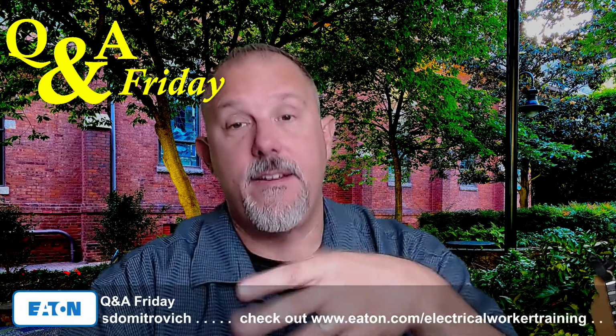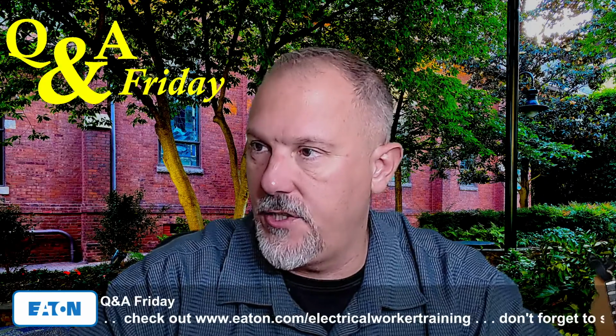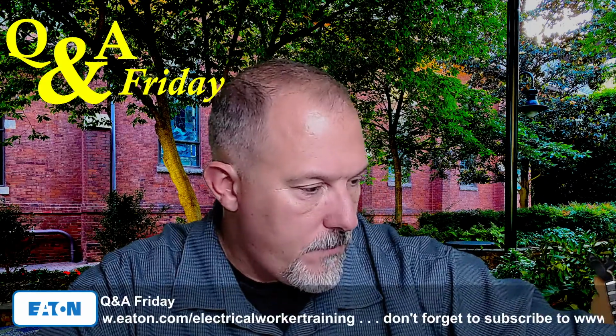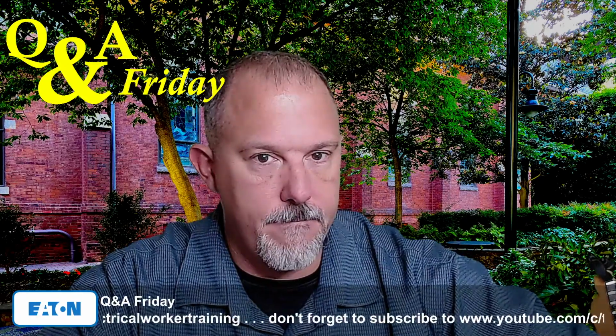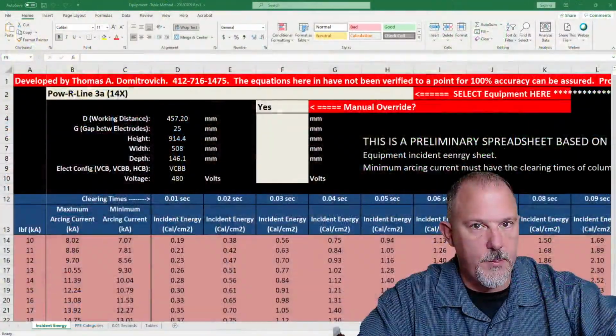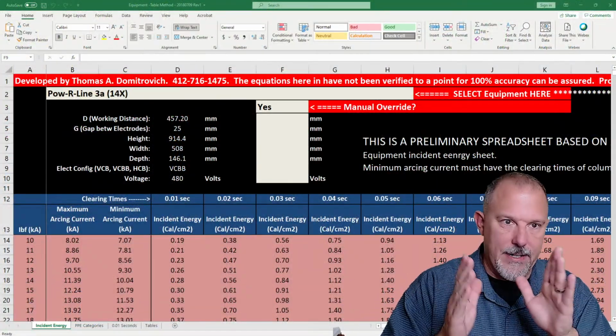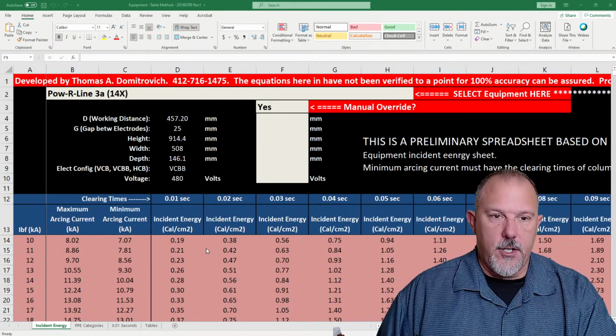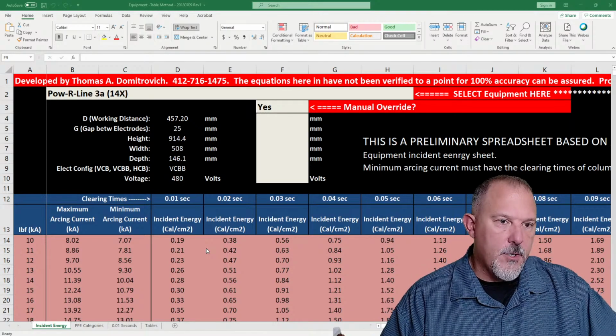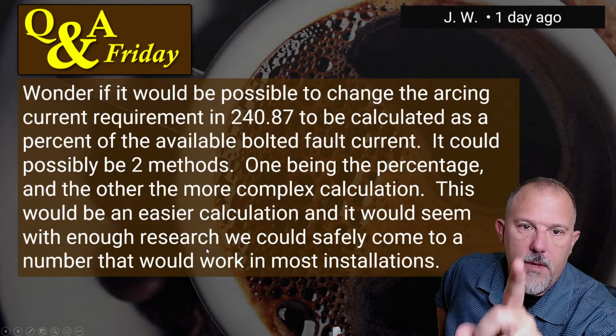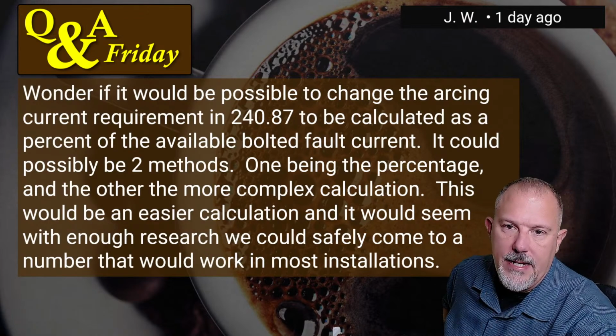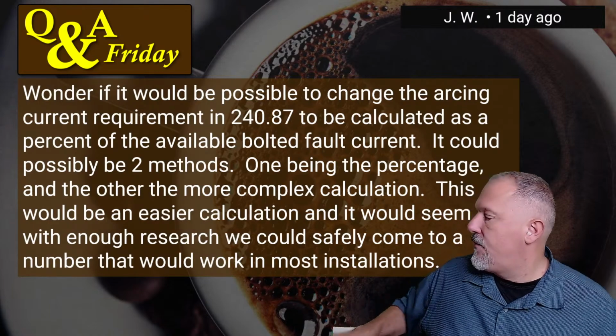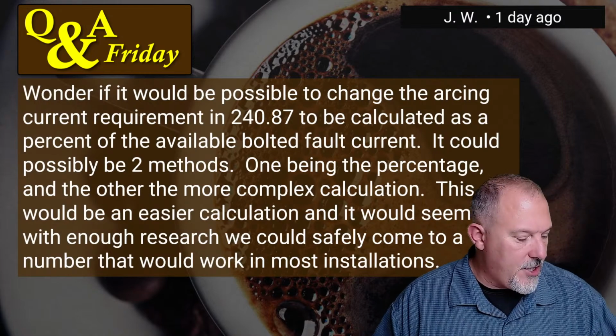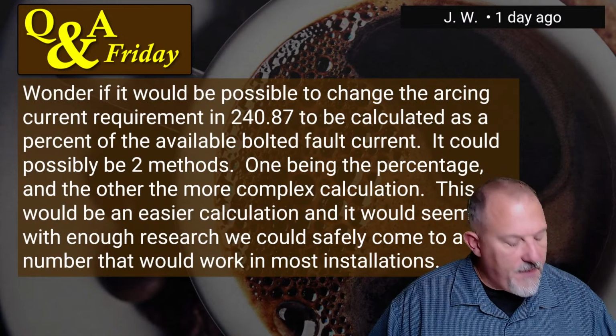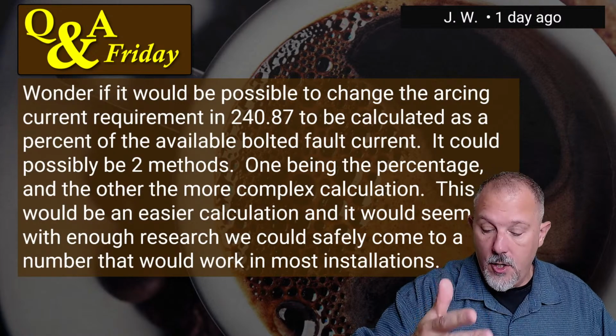So I have a spreadsheet, and if I make any changes, I'd like to make sure everybody has a copy of those changes. So here's my spreadsheet. Now I don't want to scare anybody, but I know it's busy. So let's talk about arcing current. The person in the question said the arcing current requirement in 240.87 should be calculated. So let's look at 240.87. My concern with 240.87 is it just says arcing current. If you understand IEEE 1584, how do you calculate arcing current?